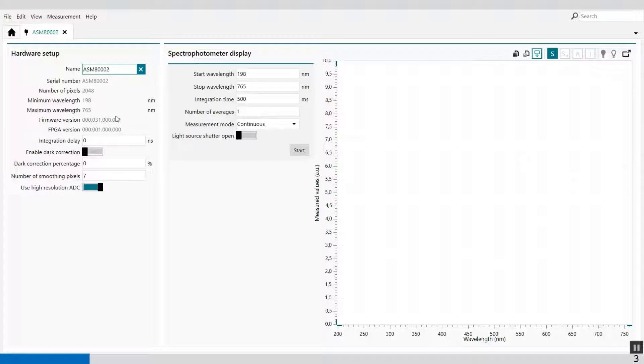Then we have the integration delay — an input field which can be used to specify the integration delay in nanoseconds, set at zero by default. This delay time corresponds to the time between the detection of the TTL trigger pulse required to acquire a spectrum in the digital in-and-out trigger mode and the start of the integration cycle of the spectrophotometer.